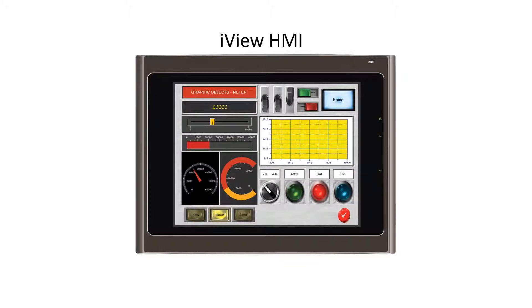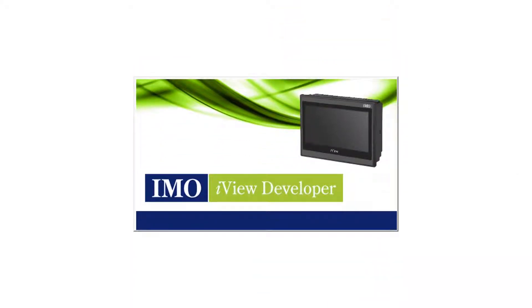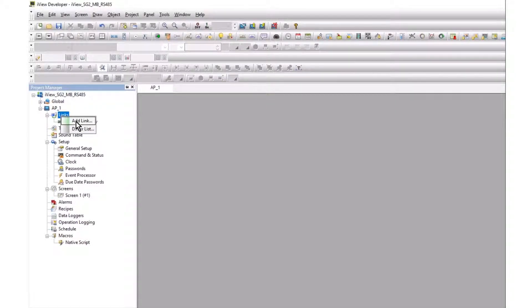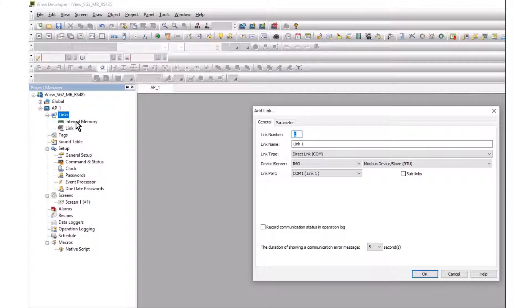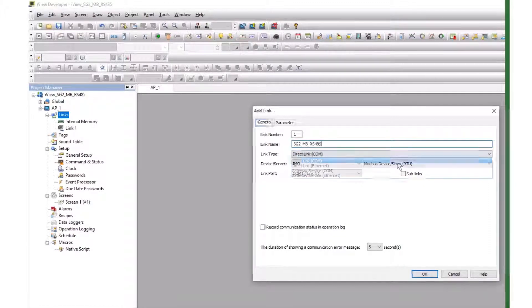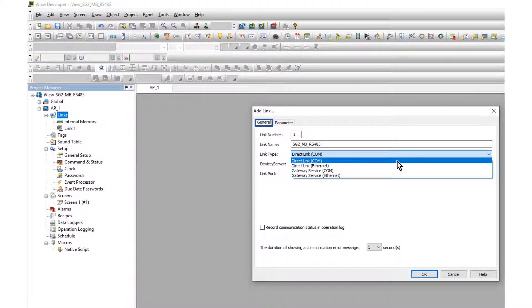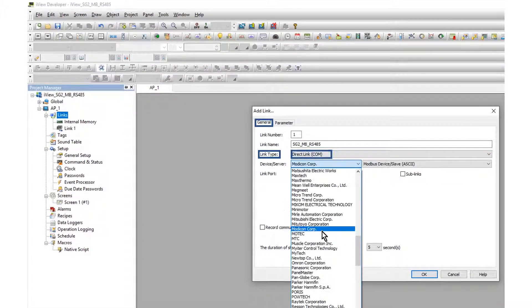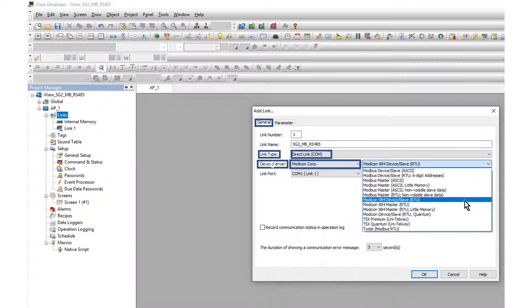The iView HMI is configured to match the SG-2. From the Link selection, right-click and select Add Link. The Add Link dialog will open. Name the link. The link type is Direct COM, the link device is Modicon, and the protocol is Modicon 984 Device Slave RTU.